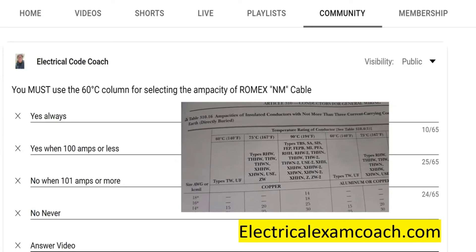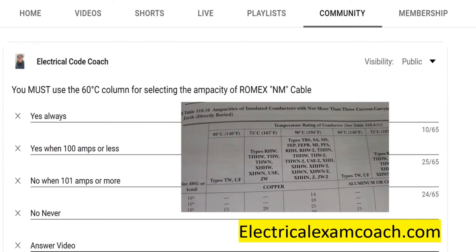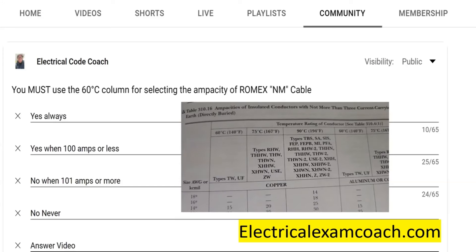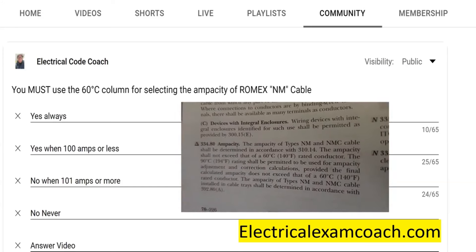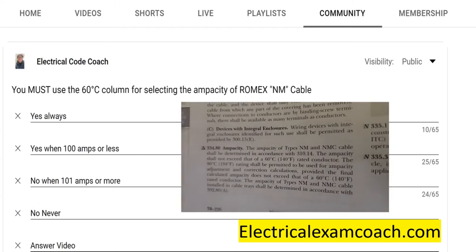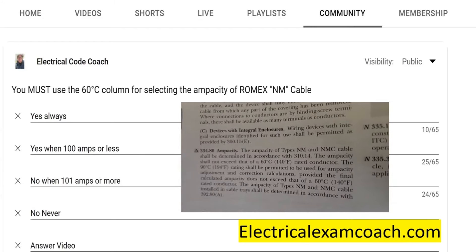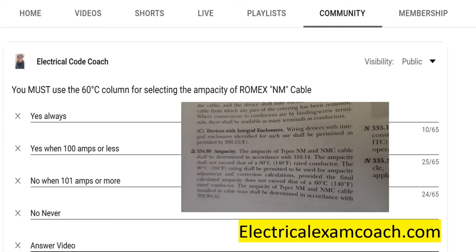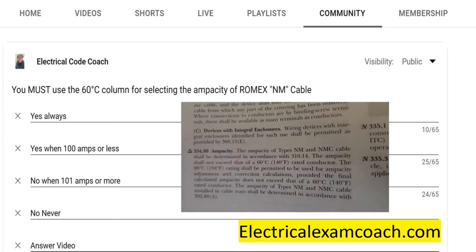The first place we have to start is in our primary ampacity table, and if you look closely, you won't find type NM cable listed anywhere. So where do we find our ampacity from? It's actually found in 334.80, and it states that we must select from the 60 degree C column when using type NM cable. Unless we are doing bundling adjustments or temperature corrections, then we're allowed to select from the 90 degree C column for those applications only.